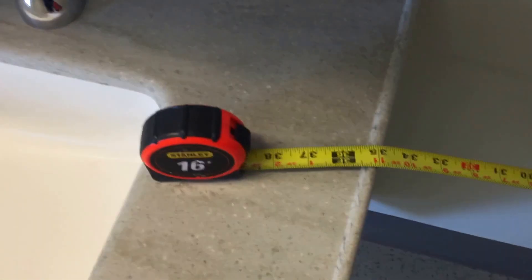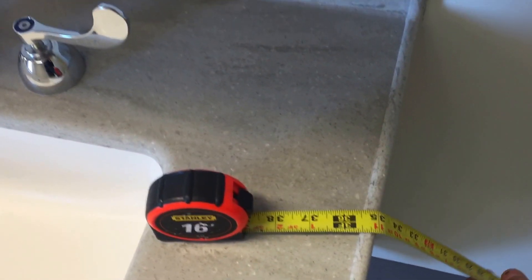And that's because that receptacle is right next to this sink. In fact, if I show you my tape measure, it's only about three feet away from the outside edge of that sink, and that's where the violation comes in.